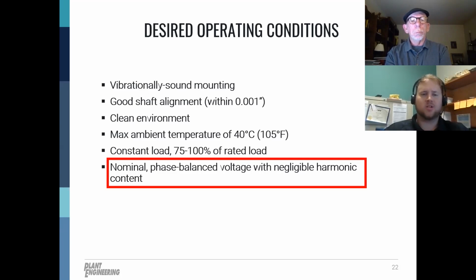Third, ideal operating condition, you want a clean environment for your motors. Now, I know, like we talked about earlier, this isn't a reality in a lot of cases. It's not always possible given the application, but generally, you need to make sure the motors are kept free from contaminants entering them. If it's a fan cooled machine, keep the fan shroud unblocked so air can move across the motor for proper cooling. And then also, you can shut the motor down, make sure it's de-energized, and take your fan shroud off. Clean the fan blades every once in a while, especially if you're in a high dust particle area, sawmills, coal mines, areas where you're just going to have a lot of dust. But again, just make sure you de-energize the motor before you do anything like that.